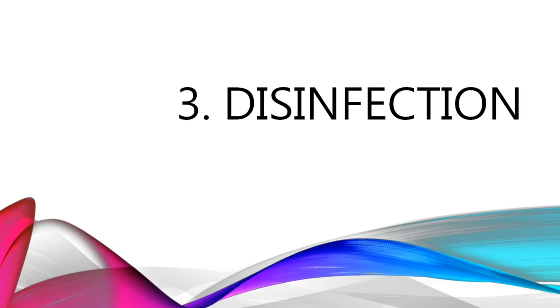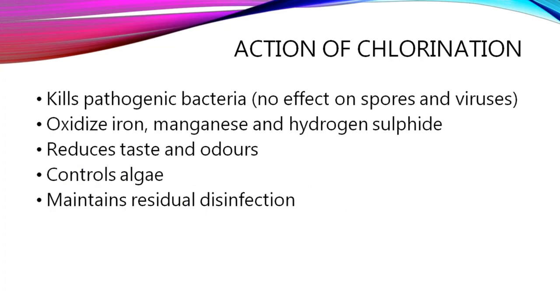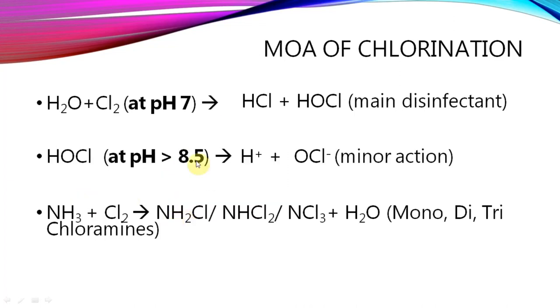The last step is disinfection, usually done with chlorine. Criteria for a good disinfectant: should not be influenced by water properties, should act within a short time, should not be toxic or impart color, water should remain potable (drinkable), should be cheap and easy to use, should leave a residual concentration to deal with contamination, and should be easily detectable. Chlorination kills pathogenic bacteria, oxidizes iron, reduces taste and odor, and controls algae. When water and chlorine combine, they form hypochlorous acid and hydrochloric acid, which then dissociate further.